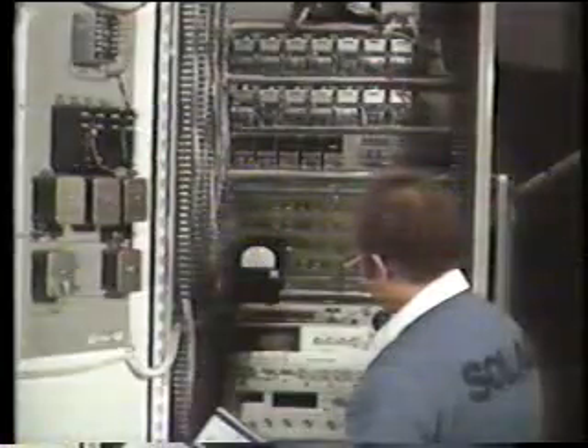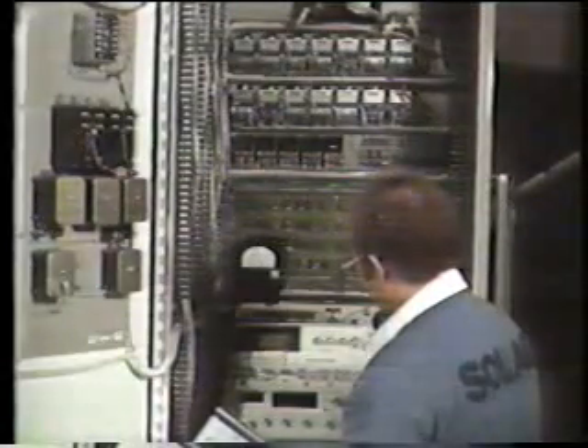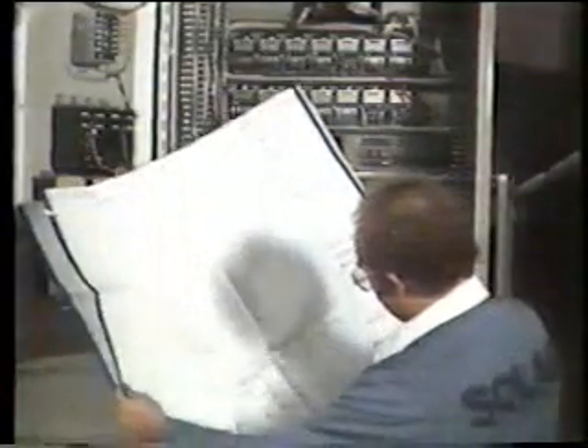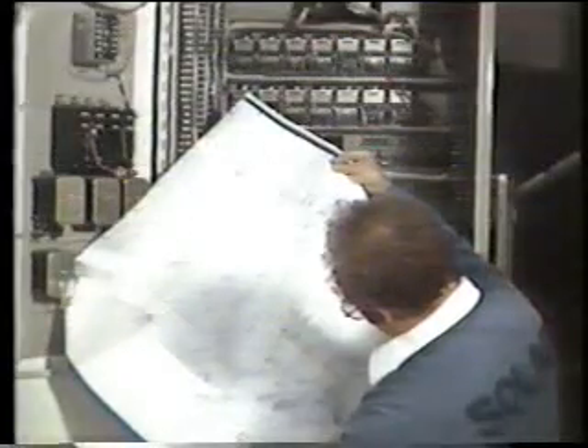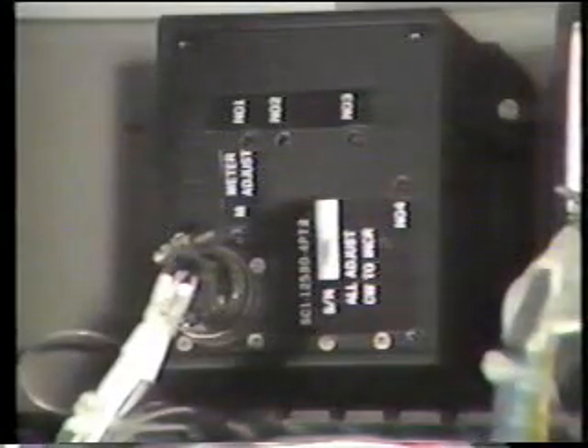Now, while the equipment is still set up, use a schematic and check that you've verified the set points of all the switch contacts in use. Some applications use both normally open and normally closed contacts on switches other than 108% speed. Be sure to verify their set points. Failure of any speed switch contacts in use is cause for replacement of the control box.